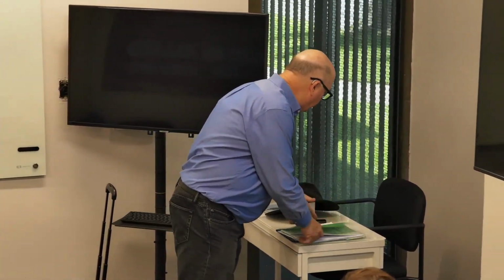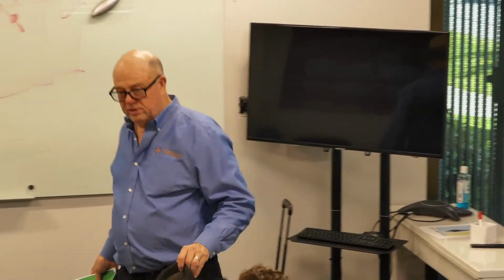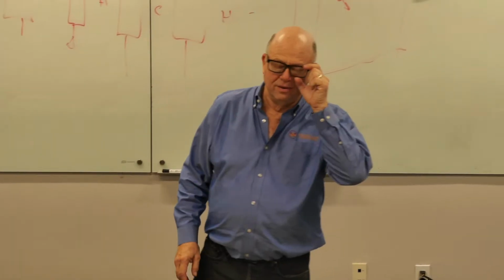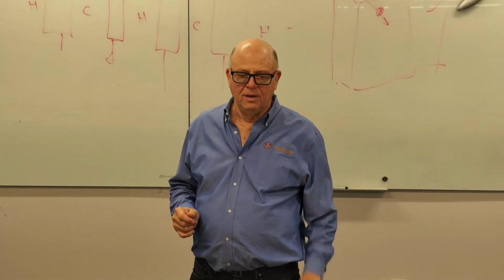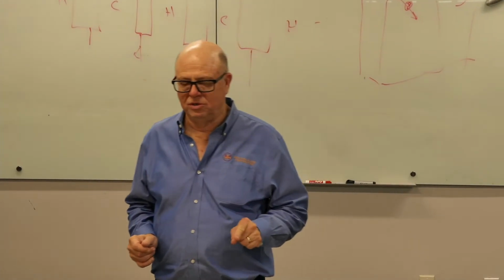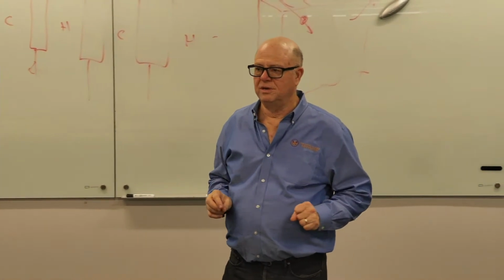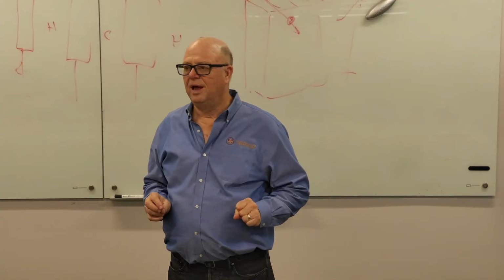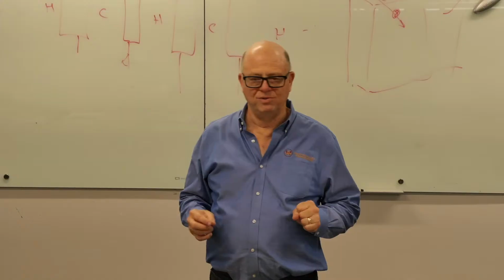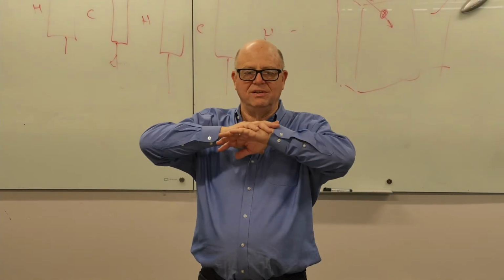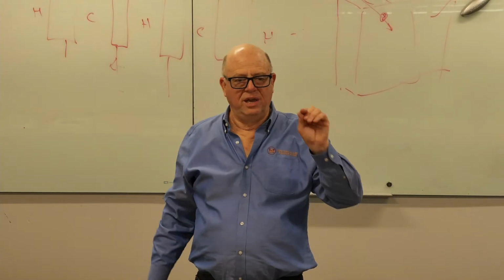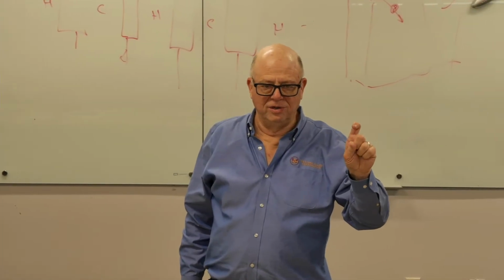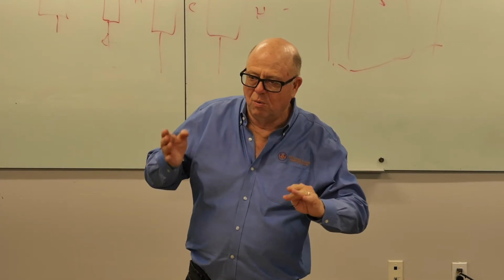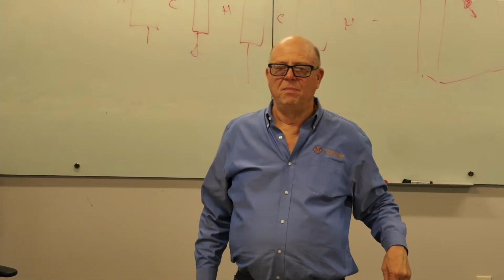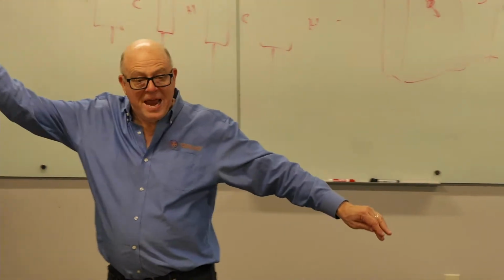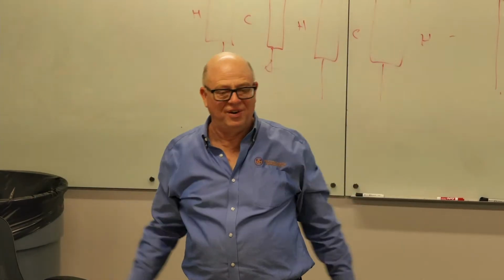I'll finish with one last little short story. When we did the Fox data center on the Fox lot, a jillion CRAC units, it was the old style data center. The last step that the electrical contractor was supposed to do was adjust all the ground fault breakers. That never happened. And so it was a preseason NFL game. I was actually watching the game on TV. And suddenly, snow on the screen because a condenser fan motor had burned out on a little condensing unit. And because the ground fault breakers were not adjusted all the way back to the main, that trip caused the main breaker for the whole distribution center to trip.